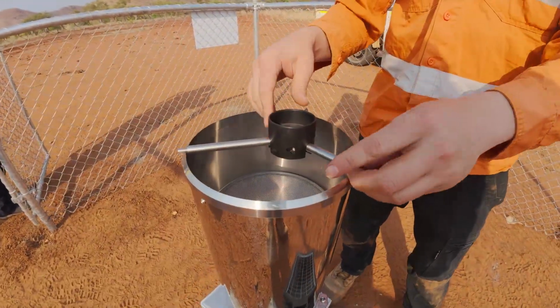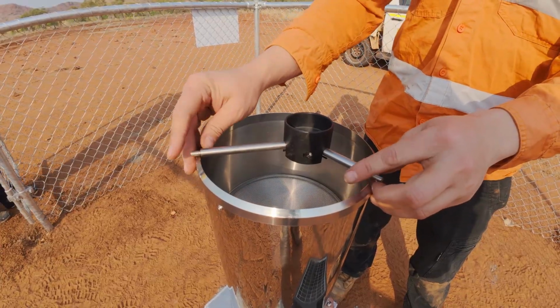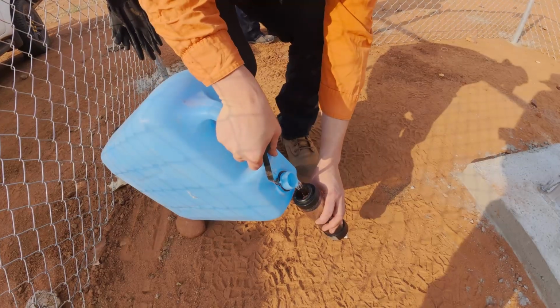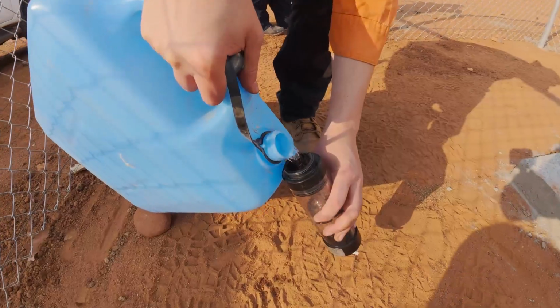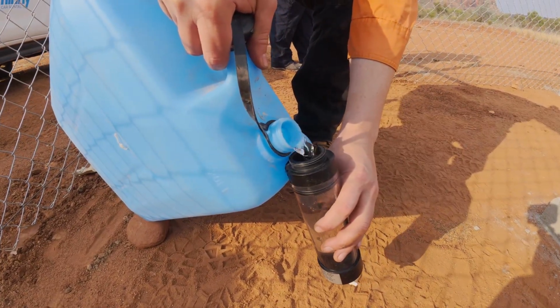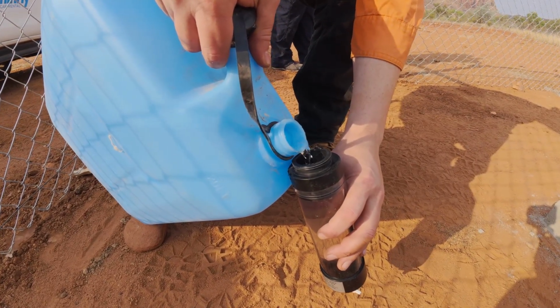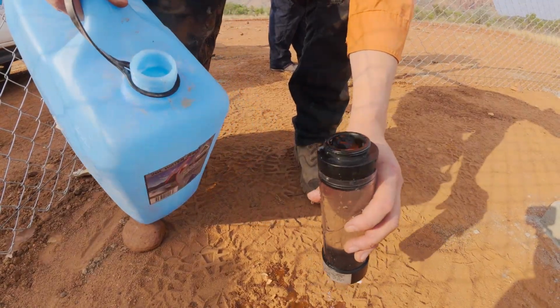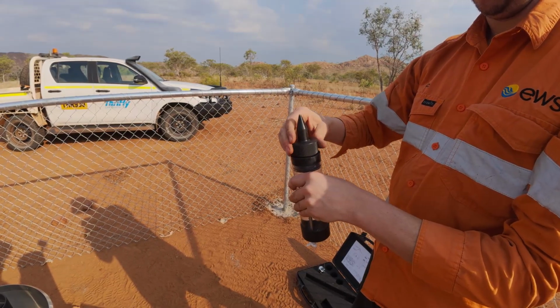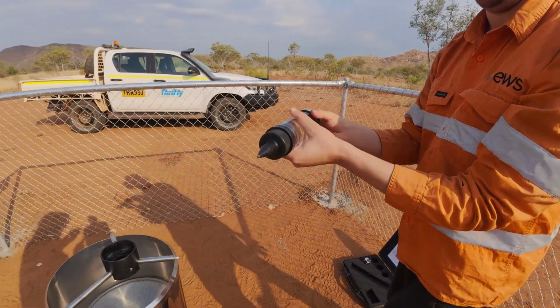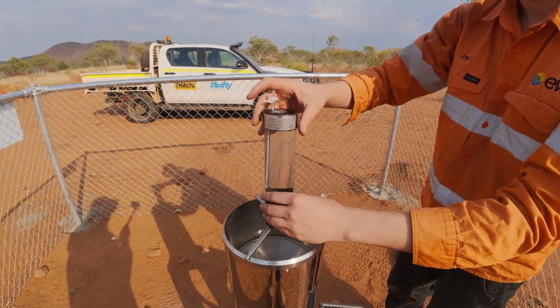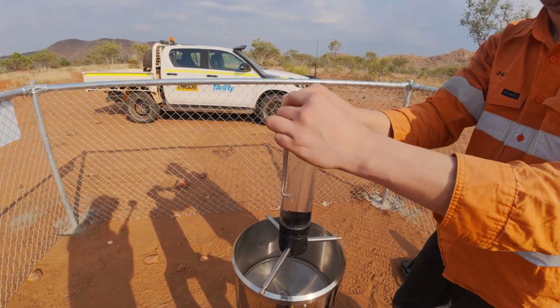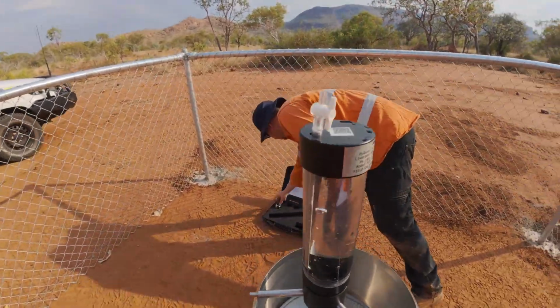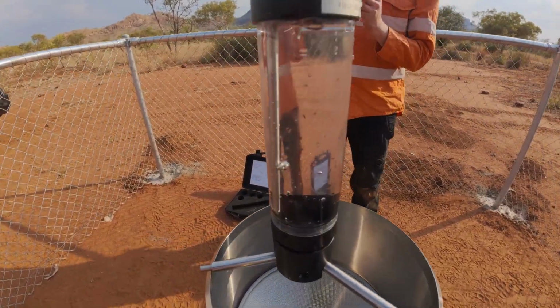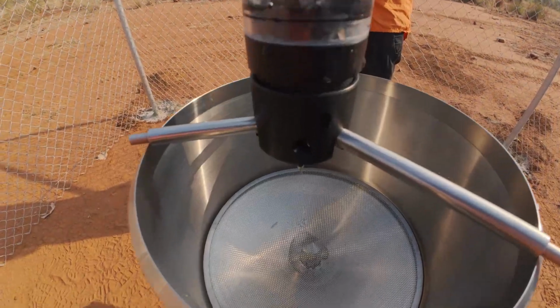Finally, we can run a calibration or accuracy check. To do this, you'll need a rain gauge calibration testing kit. Place the testing stand on the rim of the rain gauge, then fill the known volume container with water, ensuring a positive meniscus at the top of the container. Attach the funnel piece to the container and place it into the stand. The release valve is then opened, allowing water to flow into the rain gauge. We then listen for the mechanism to tip and count each tip using a tally sheet or handheld counter.